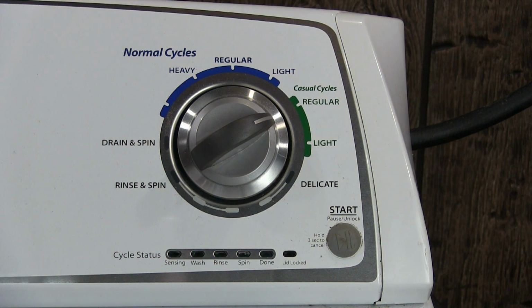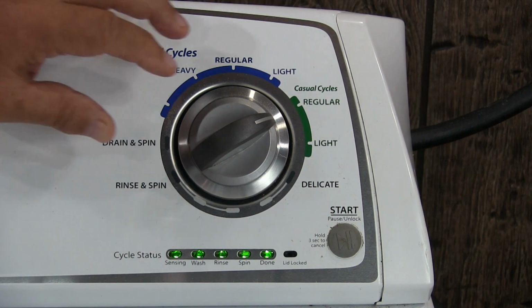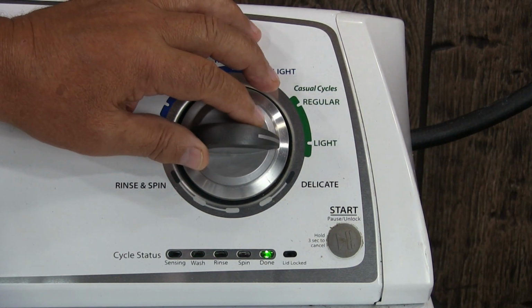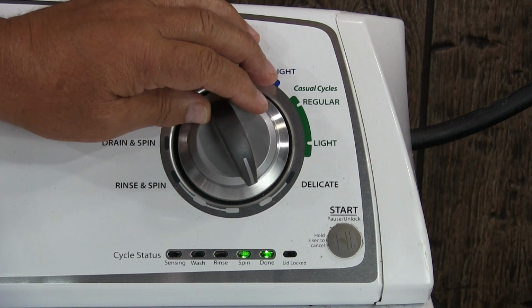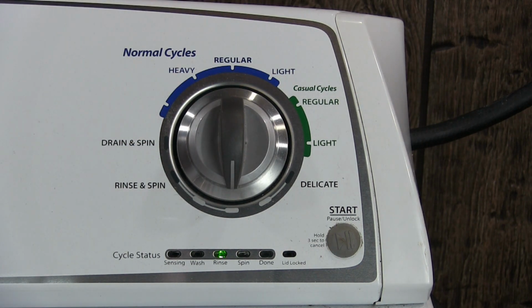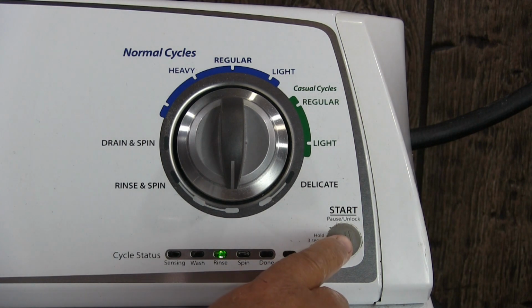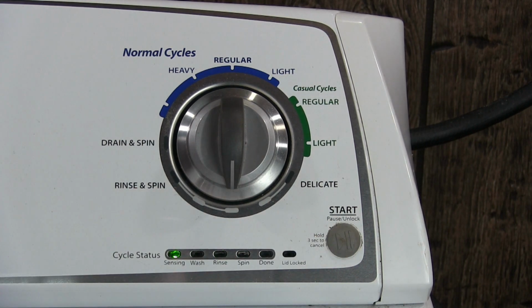mode. Turn the cycle selector knob to the right until the rinse light is on. Then push on the start button to start the calibration mode. Do not interrupt the calibration, disturb the washer, or remove the power. Otherwise, calibration must be repeated. In other words, let the machine finish the calibration mode on its own.